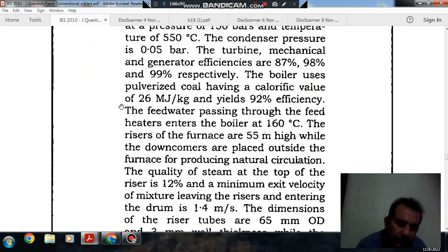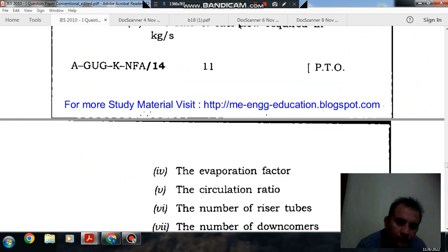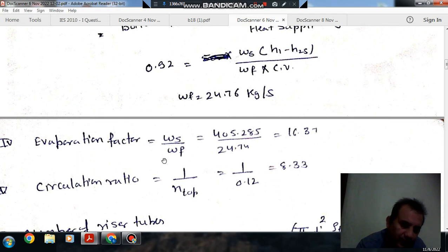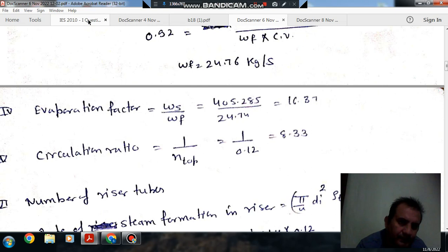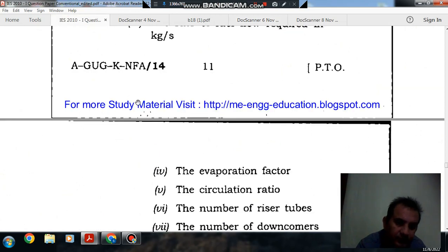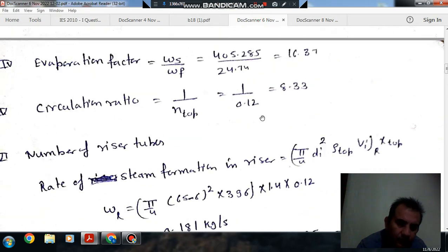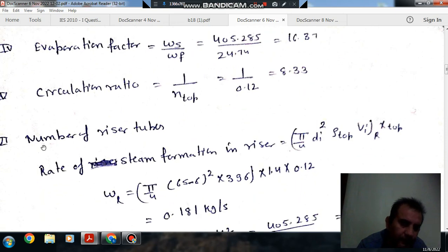Next question is evaporation factor, which is just the ratio of omega S by omega F. That comes out as 16.37. And next is the circulation ratio. Circulation ratio is 1 by dryness fraction at the top of the riser, and the dryness factor is given as 12%, so it will be 1 by 0.12, so that is 8.33.